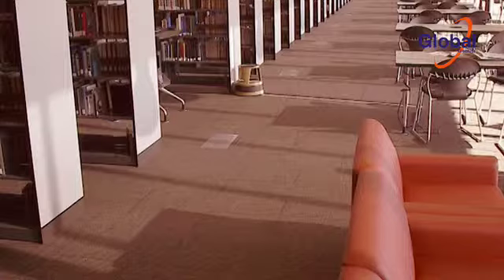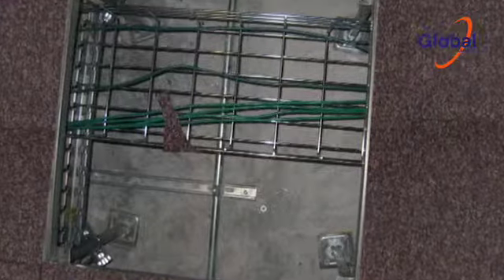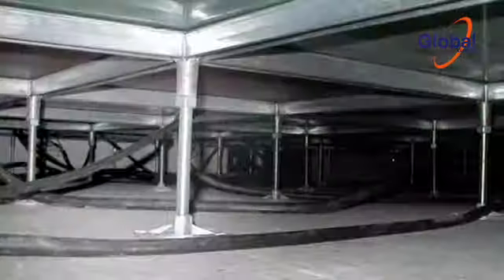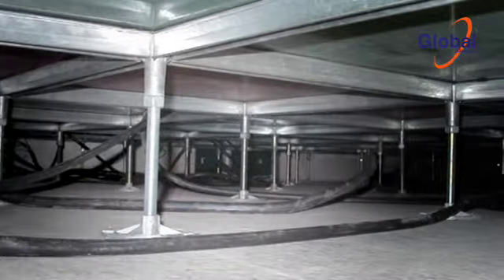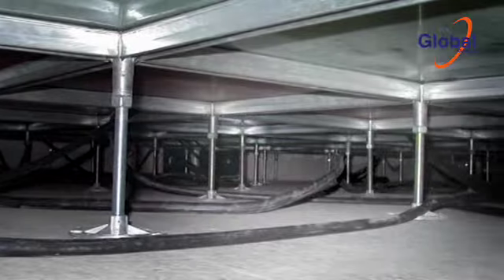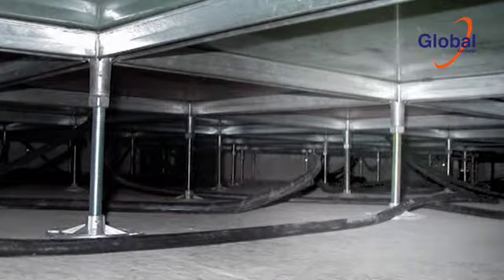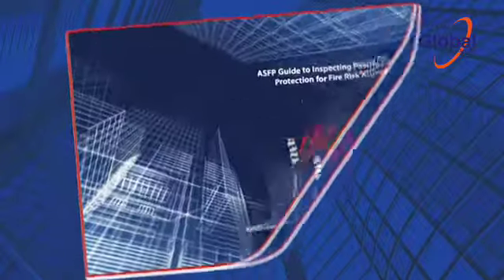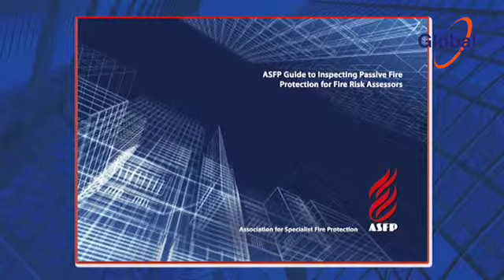For raised floors, if possible, floor tiles near the edges of fire-resisting walls should be lifted and a torch used to look for the installation of suitable cavity barriers. Any faults must always be recorded as part of the assessment report and be remedied as soon as possible. The ASFP guide and app provides guidance on performing structured fire risk assessments.